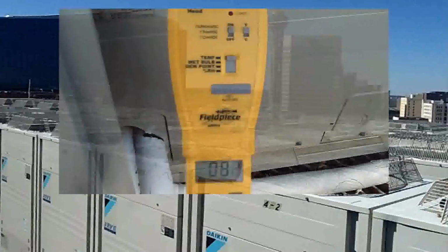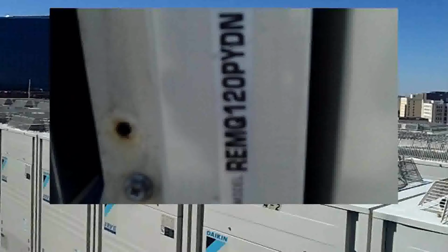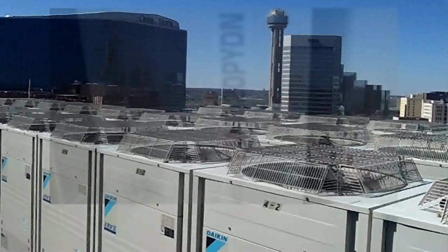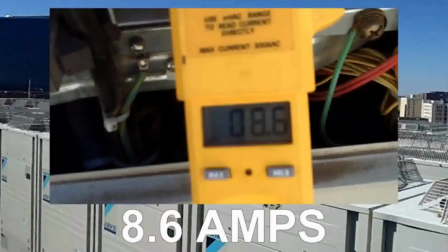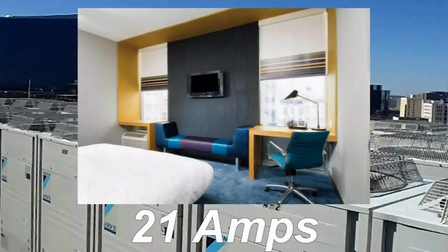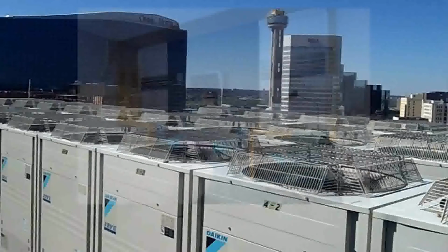On the day of our visit, it was 82 degrees. We decided to take one of the panels off one of the 10-ton modules and check the amp draw. It was 8.6 amps. One of these units would typically be hooked up to about 13 indoor units. Even if it was just hooked up to one, this would be less than what a PTAC in a standard Aloft would be drawing for one unit, which is about 21 amps.